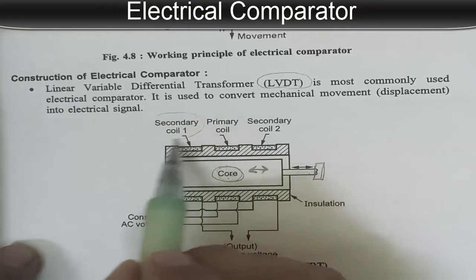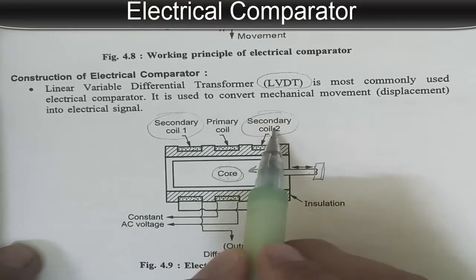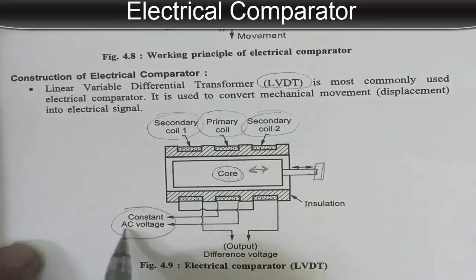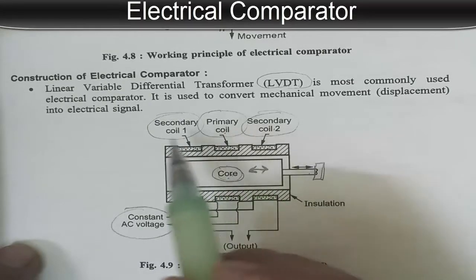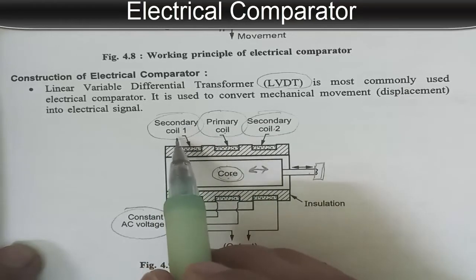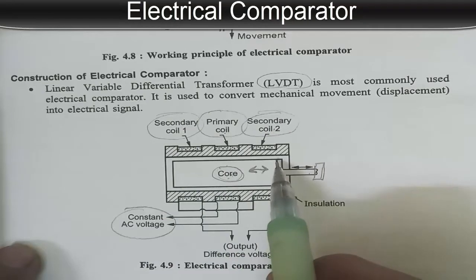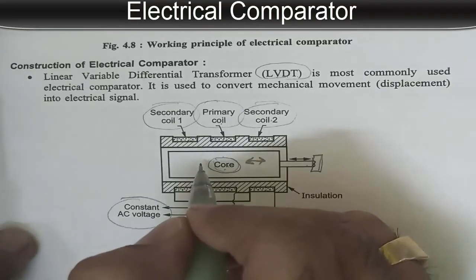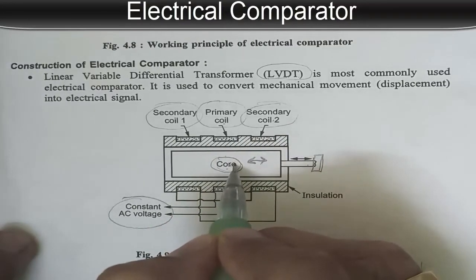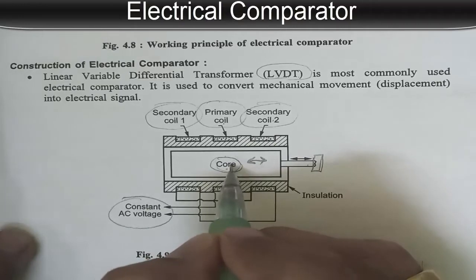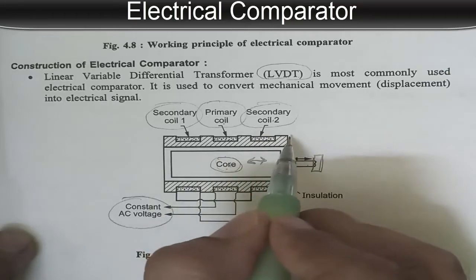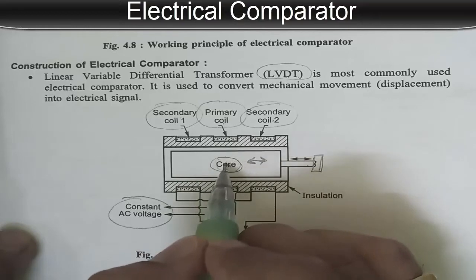Here you can see in this LVDT: secondary coil 1, secondary coil 2, and the primary coil. A constant AC voltage is given to the primary coil. At a particular distance — which will be the same on both sides — are secondary coil 1 and secondary coil 2. When the core is centralized at the middle position, between the two secondary windings, the voltage induced in each secondary coil will be the same.